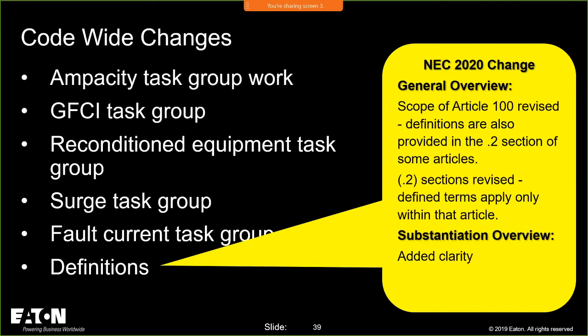Finally, in the definitions—we talked a little about this. The problem was some definitions in the .2 areas of the National Electrical Code were being referenced and used in other articles. Say a term was used in Article 555 and defined in 555.2, but not in Article 100. Somebody was using that same term and definition for something over in 690 for PV. Historically, that would cause confusion, because they'd say you can't use that term—you have to go to Merriam-Webster, because that term in 555 only applies to 555.